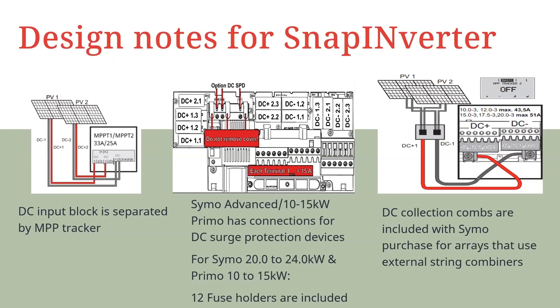When exactly would fusing be required for a string? Overcurrent protection fuses protect the conductors and the modules in the case that a string faults with another current, or faults with another string and begins backfeeding current. The expected DC current could be three times greater than expected when these faults occur. The best rule of thumb is that systems with three or more strings input to the same maximum power point tracker will require fusing. Please see NEC code 690.8 for more information on these calculations. That rule of thumb is true for about 99% of the systems.